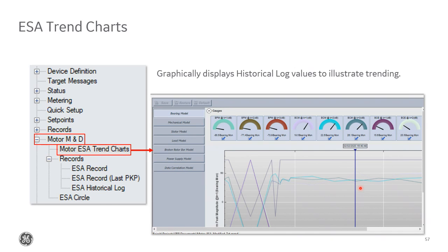Something new in firmware 2.7 is we added this motor ESA trend charts option. These trend charts basically graph the historical log values for each of the three fault categories so that you can more easily visualize how the values are fluctuating over time. If they seem to be slowly increasing, which could mean a problem may be creeping up, or if everything is staying relatively consistent.